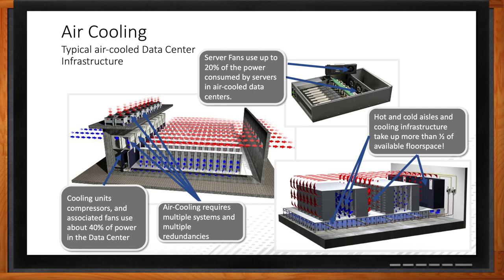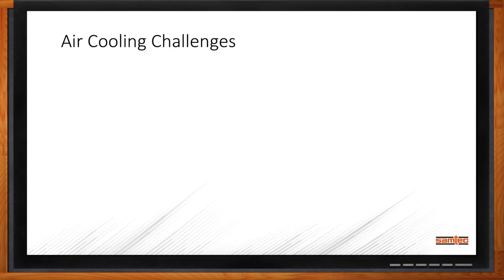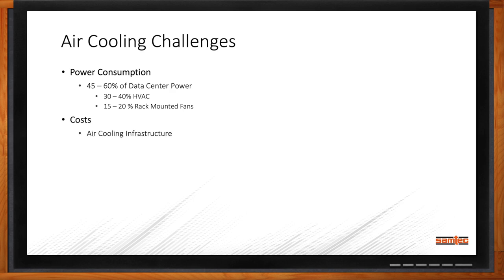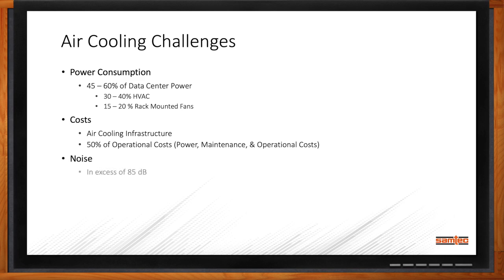Looking at the biggest challenges of air cooling: about 45 to 60 percent of a data center's power consumption is going to come from your HVAC and rack-mounted fans. The overall cost for a cooling infrastructure — just as an HVAC replacement at home can be costly, take that to industrial scale and you're adding significant cost. About 50 percent of your overall cost is going into power, maintenance, and operational costs. And that's not even mentioning the additional noise from all the fans running, which can be in excess of 85 decibels.